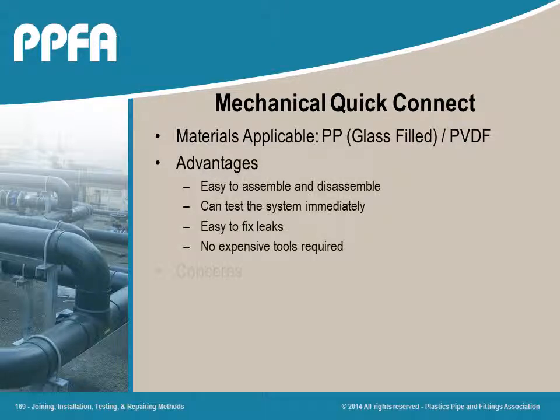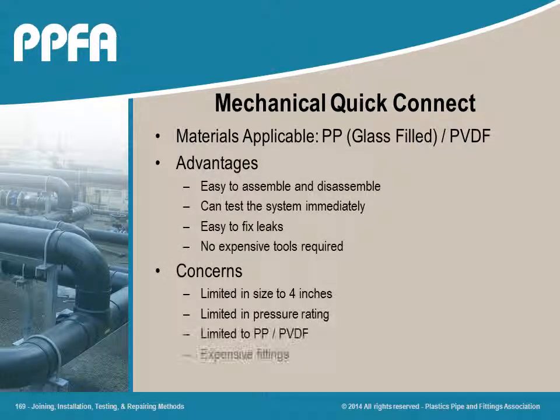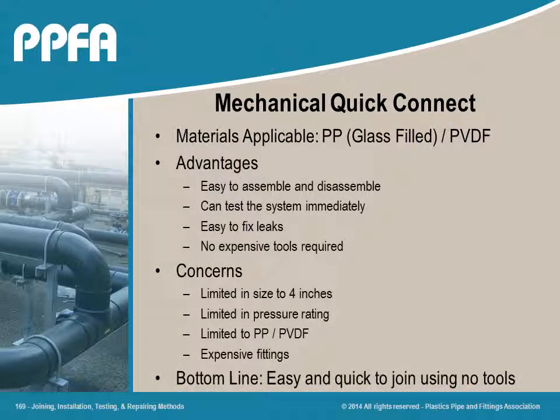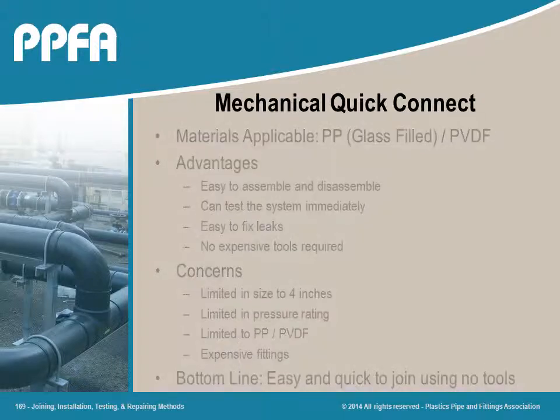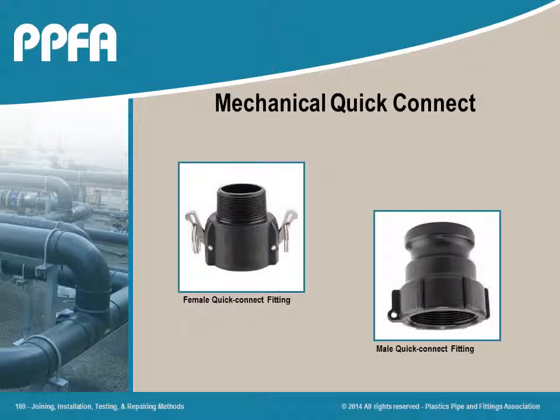The quick connect and disconnect system of joining has been successfully used in industrial applications for over 3 decades. It has similar advantages and limits as the push-fit joining system, except this system can go up to 4 inches in diameter. The present materials being offered with this system are glass-filled polypropylene and polyvinylidene fluoride.